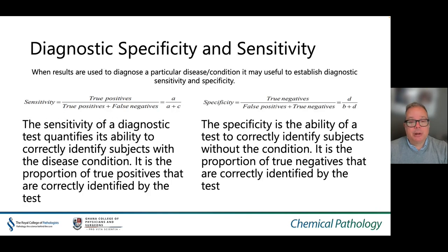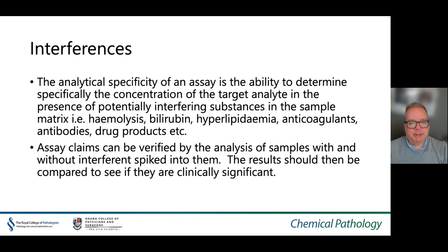When results are used to diagnose a particular disease or condition, it may be useful to establish diagnostic sensitivity and specificity. The sensitivity of a diagnostic test quantifies its ability to correctly identify subjects with the disease — it is the proportion of true positives correctly identified. The specificity of a test is its ability to correctly identify subjects without the condition — the proportion of true negatives correctly identified. The analytical specificity of an assay is the ability to determine specifically the concentration of the target analyte in the presence of potentially interfering substances such as haemolysis, bilirubin, hyperlipidaemia, or anticoagulants. Assay claims can be verified by analysing samples with and without interference spiked in, and the results compared to assess clinical significance.